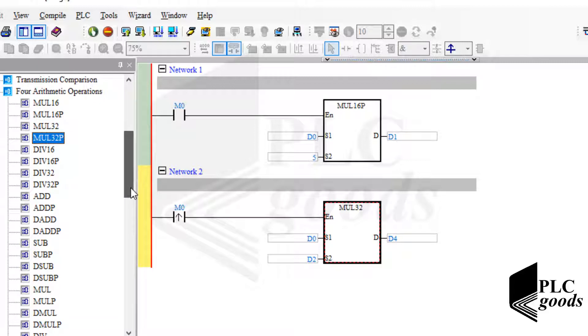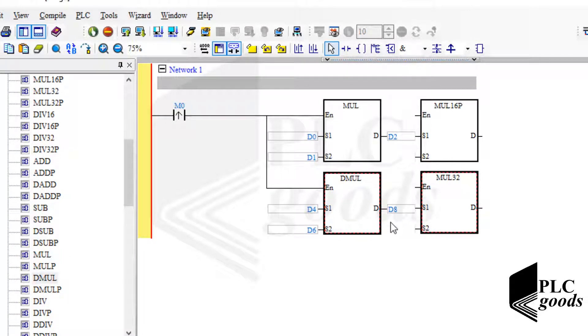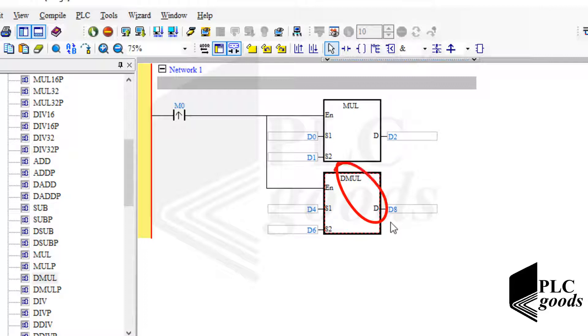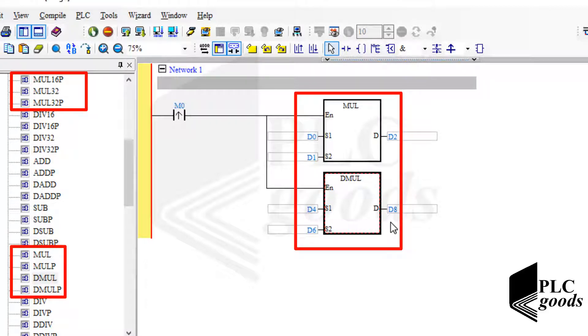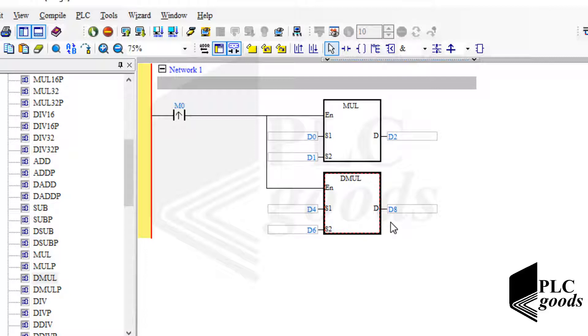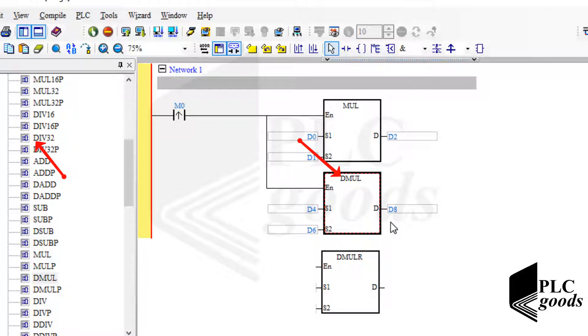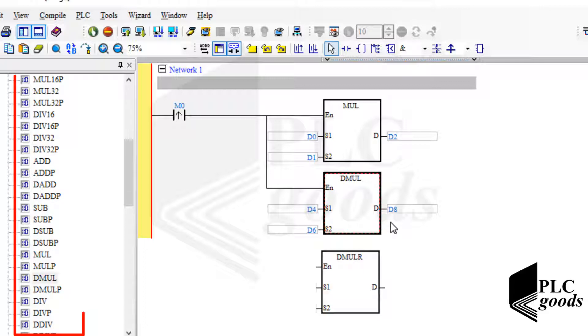MUL and DMUL instructions work like MUL16 and MUL32, but they use more bits to store their result. MUL uses 32 bits and DMUL uses 64 bits. So this instruction uses D8, D9, D10, and D11 to store its result. Note that all explained instructions work with integer numbers. To multiply two real numbers, there is another instruction: DMULR. You can easily understand the differences between instructions. The letter D indicates that the selected instruction needs double words — 32 bits. The letter P is used for instructions sensitive to positive signal edges. The letter R refers to real numbers. You can learn other arithmetic instructions similarly.